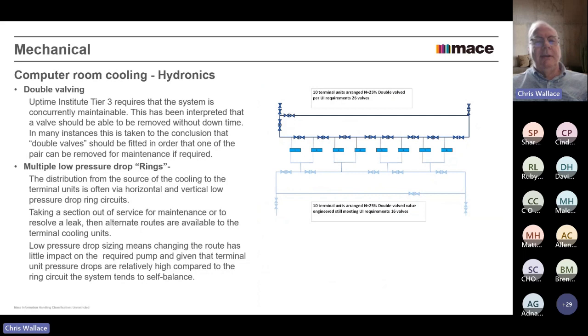foibles: quite often, Uptime Institute Tier 3 requires that the system is concurrently maintainable. Sorry, not fault tolerant, concurrently maintainable. So some people have interpreted this to mean that for every valve that you have, you should be able to take the valve out without downtime. So what they're then saying is you'll need two valves. So this growing trend, which I pull my hair out and fight tooth and nail, where everywhere you have a valve, you put two valves. And I just cannot see it. I can't understand why people believe that if you've got one valve in a circulation system and it's broken for some reason, that if you had another spare valve next to it, that won't break for some reason.